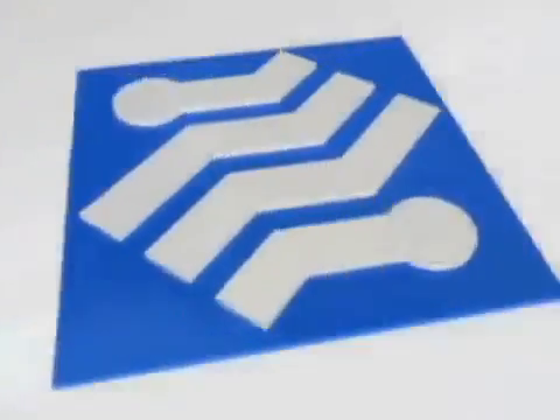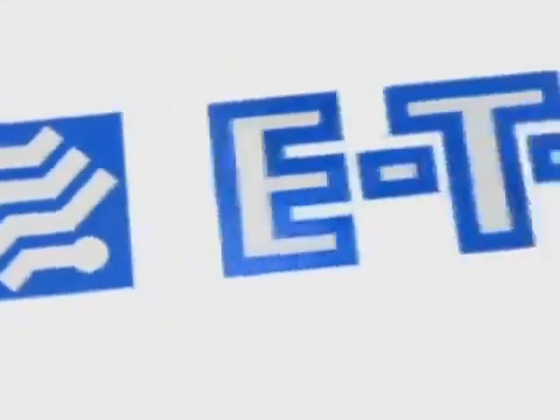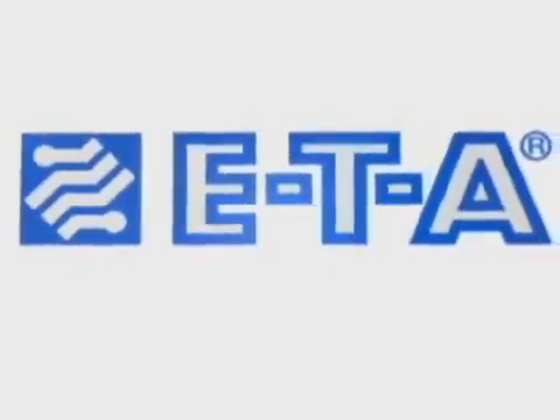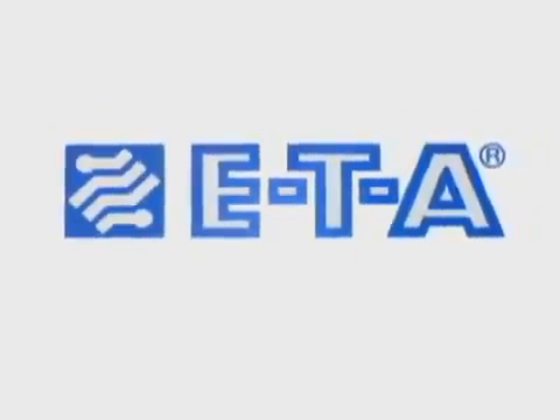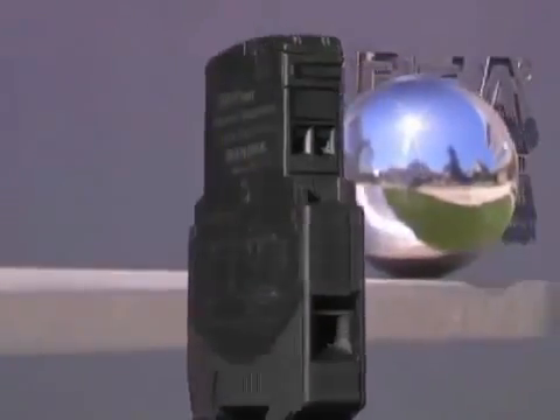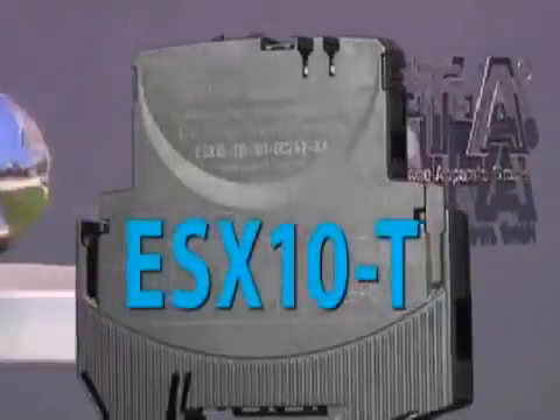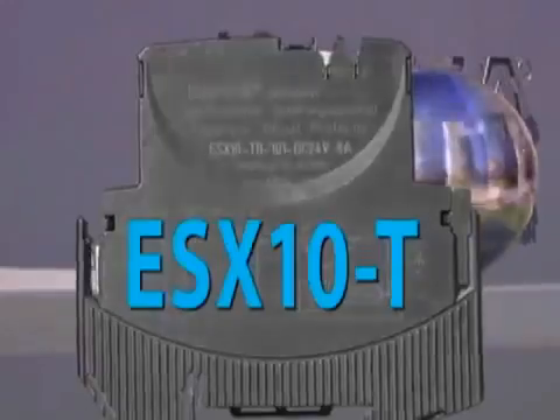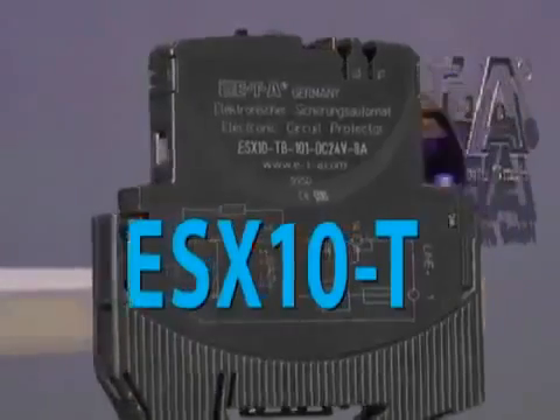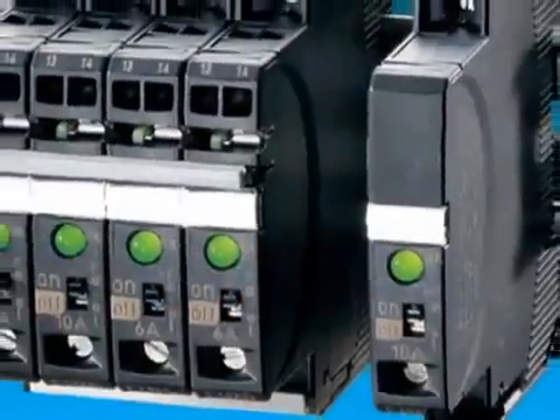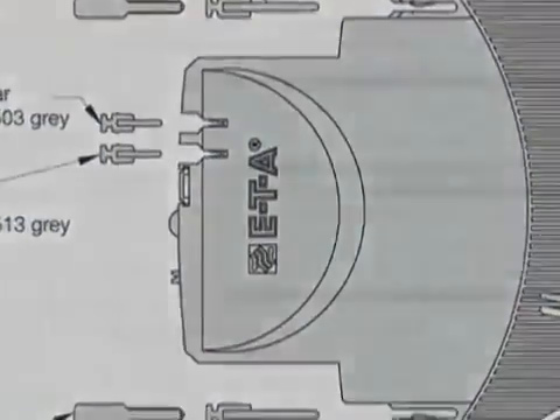ETA is the world's leading circuit breaker manufacturer and the only company that can introduce an innovative electronic circuit protector that represents a major step forward in circuit protection technology. ETA has reinvented the category, utilizing smart circuit protection technology with the ESX10T electronic circuit protector for 24-volt DC circuits. The ESX10T is transistor-based, and the disconnection of a load is done electronically rather than mechanically.